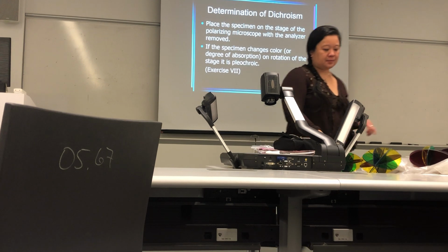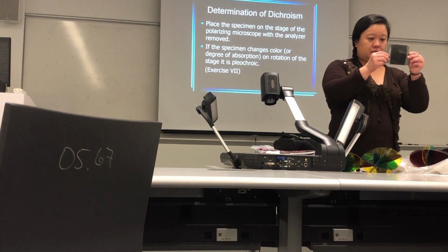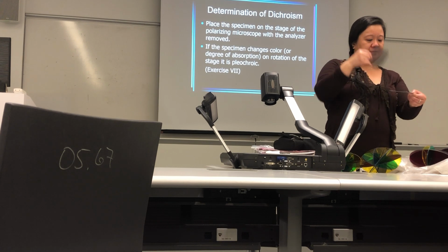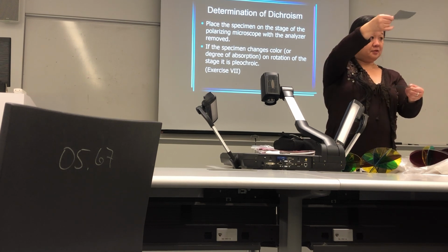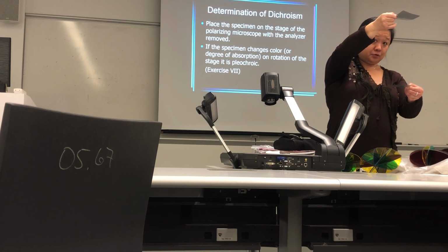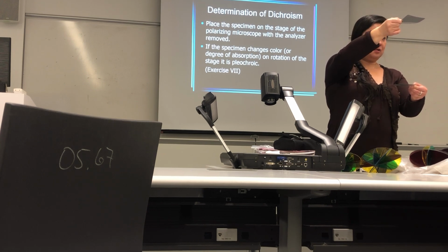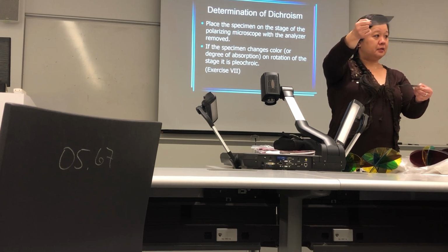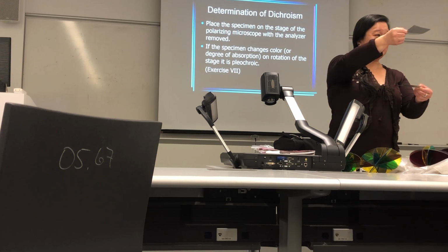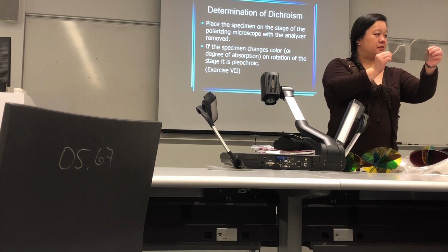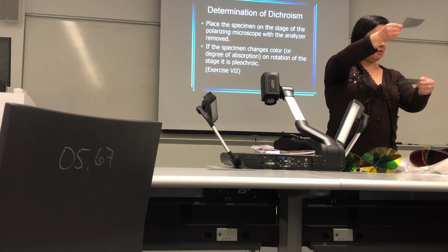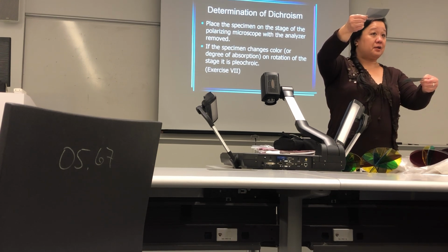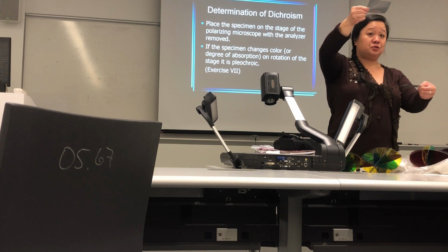When you're using the polarized light microscope, that's your, let's say, filter in the bottom of your condenser, and then you have the analyzer in the intermediary tube. You can examine any sample with the analyzer out of the field of view. When you look for a pleochroic fiber, you do not need the analyzer in the path, because when you put the analyzer in the path, you get an interference color. I'm not talking about interference colors, I'm talking about colors that are a matter of absorption because of the light that's being used to illuminate it.